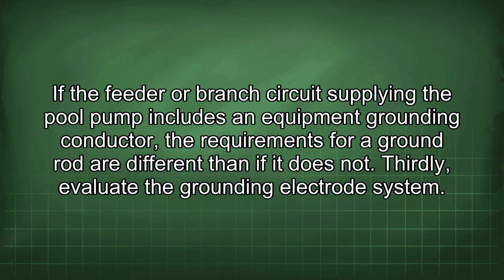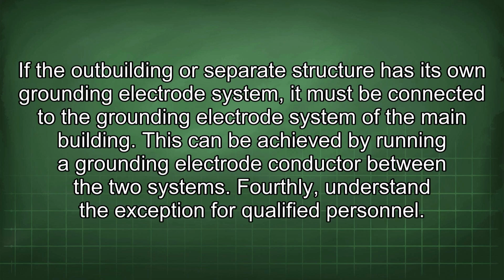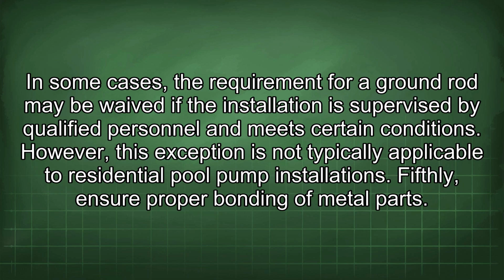Thirdly, evaluate the grounding electrode system. If the outbuilding or separate structure has its own grounding electrode system, it must be connected to the grounding electrode system of the main building. This can be achieved by running a grounding electrode conductor between the two systems. Fourthly, understand the exception for qualified personnel. In some cases, the requirement for a ground rod may be waived if the installation is supervised by qualified personnel and meets certain conditions. However, this exception is not typically applicable to residential pool pump installations.